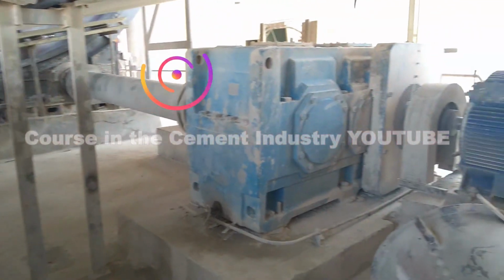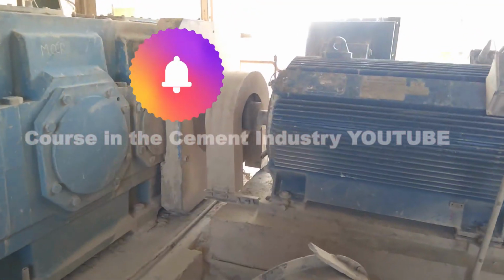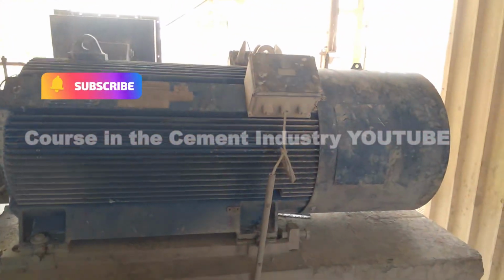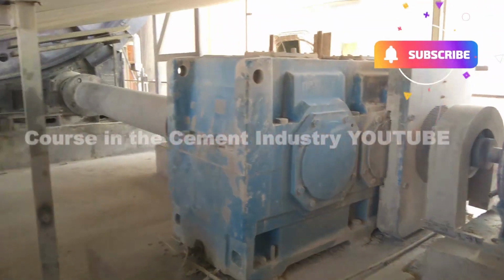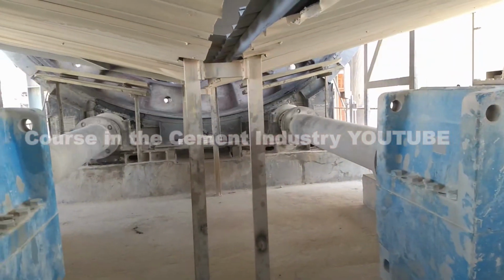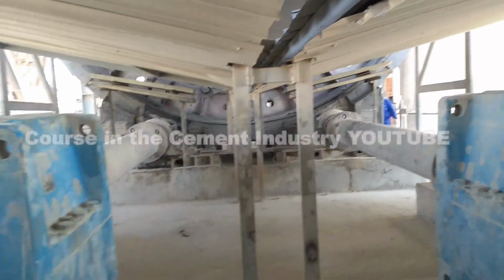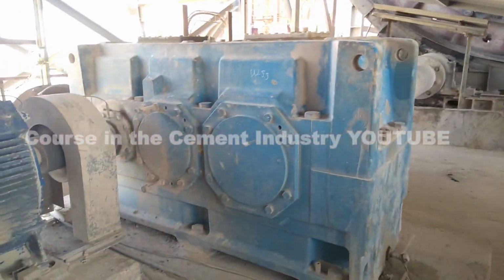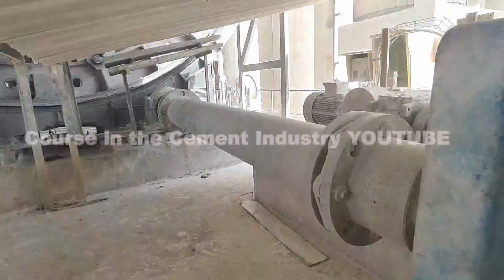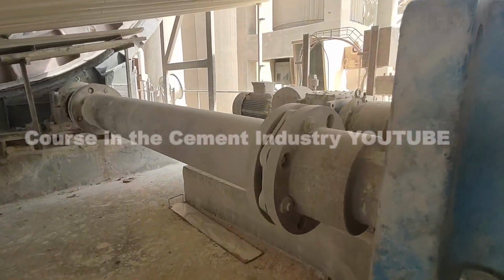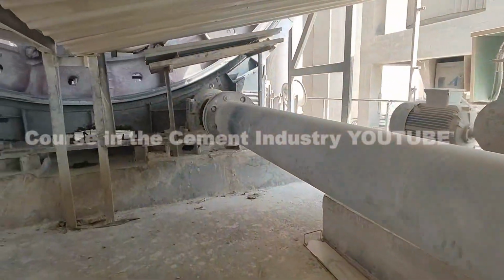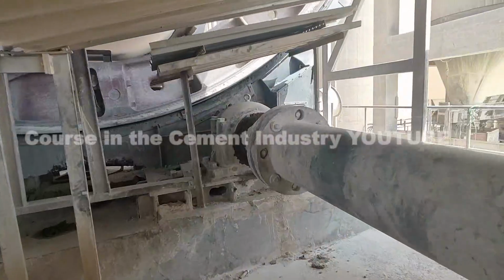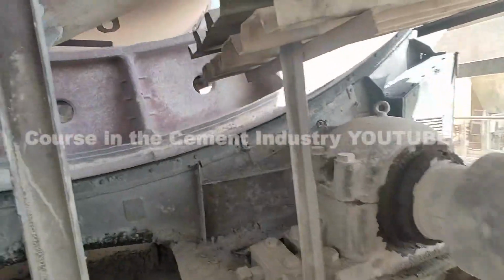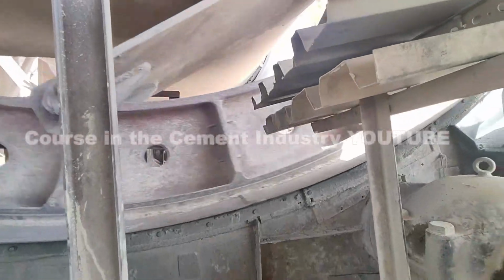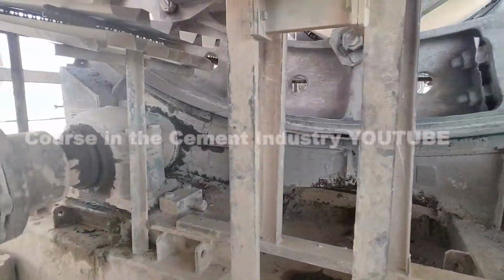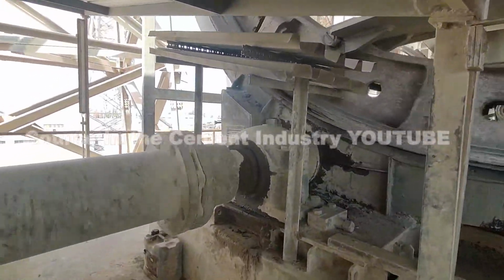Variable speed. It is crucial that the motor speed can be adjusted, for example 0.5 to 5.0 revolutions per minute, to match the feed rate and chemical conditions inside the rotary kiln. 2. The main gearbox, reducer. Function: since the motor spins at high speeds, for example 1000 to 1500 revolutions per minute, and the rotary kiln rotates very slowly, the gearbox reduces the speed while drastically increasing the torque. Lubrication: these gearboxes have dedicated oil cooling and filtration systems to handle the heat generated by the massive friction.